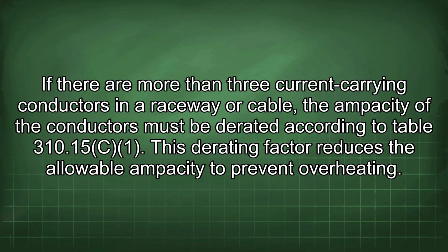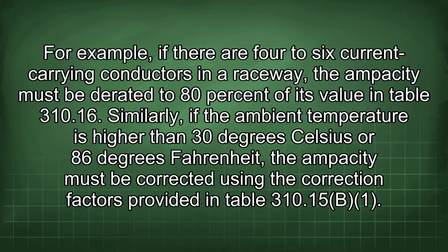If there are more than 3 current-carrying conductors in a raceway or cable, the ampacity of the conductors must be derated according to Table 310.15. This derating factor reduces the allowable ampacity to prevent overheating. For example, if there are 4 to 6 current-carrying conductors in a raceway, the ampacity must be derated to 80% of its value in Table 310.16.